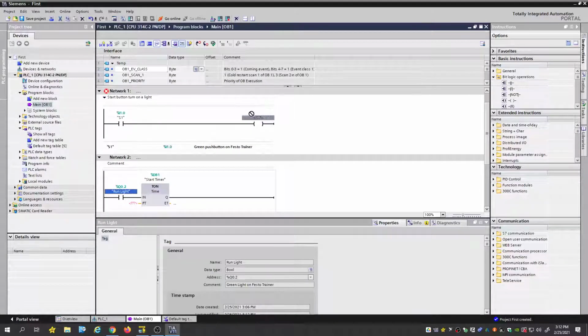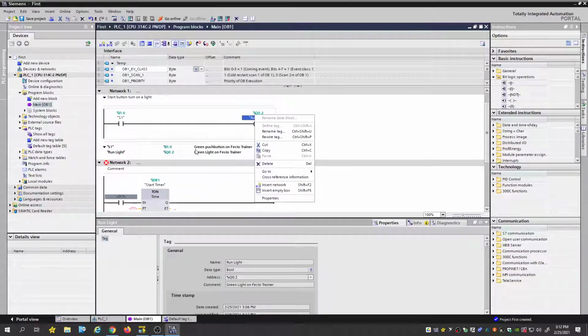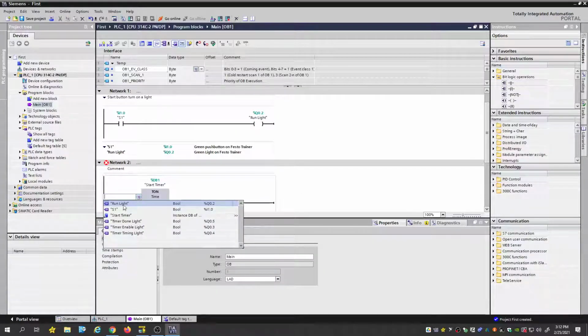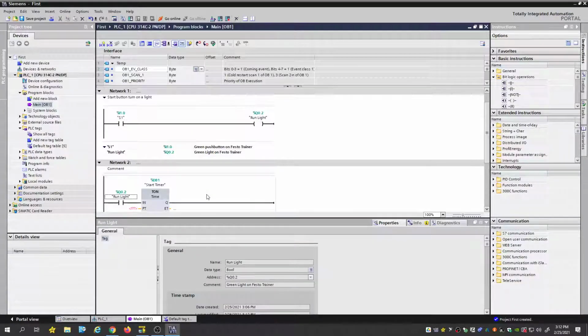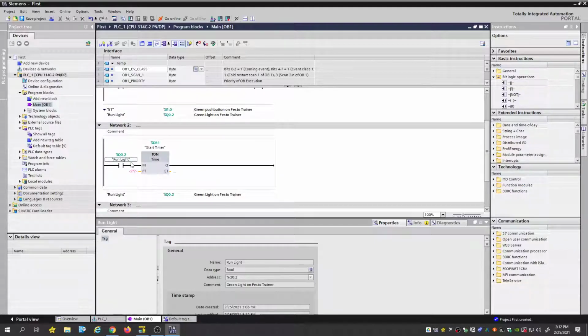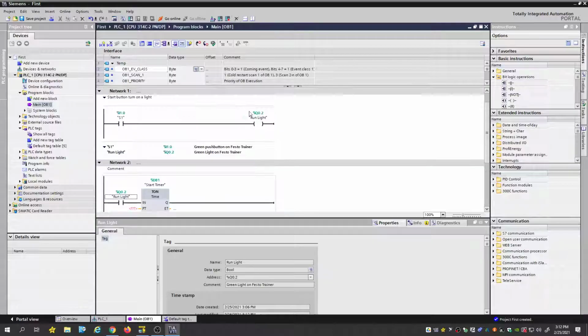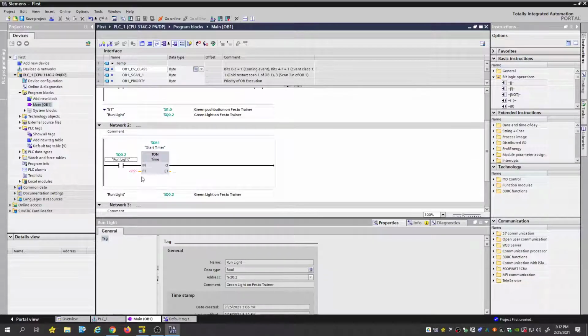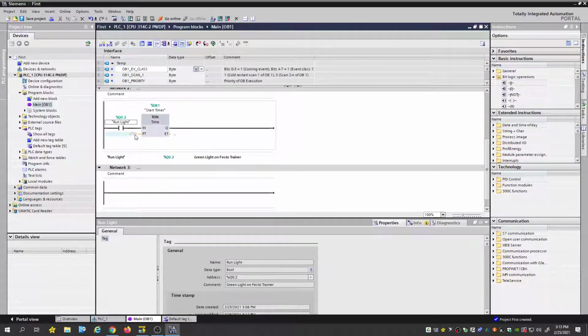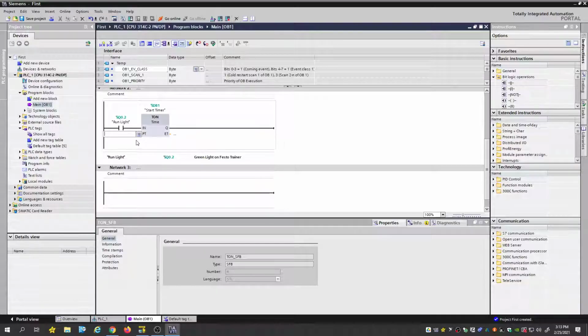Oh, I thought maybe you could, maybe it doesn't like for you to steal it. So I'm a little bit green with Siemens, but I'm used to doing things in Allen Bradley. Now our run light will energize our timer on delay. When we press start, the timer will be enabled. Depending on what our preset value, or time set, which is our PT here, is, when that's reached, our Q will go done. So right here on PT, let's say we want to do 10 seconds.